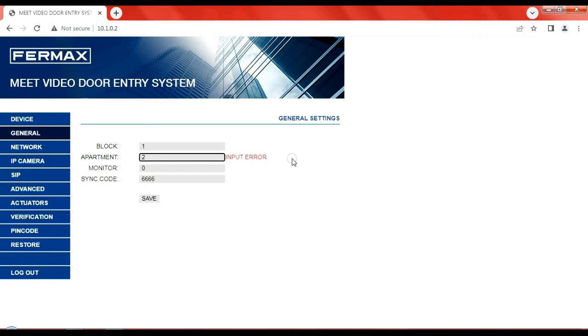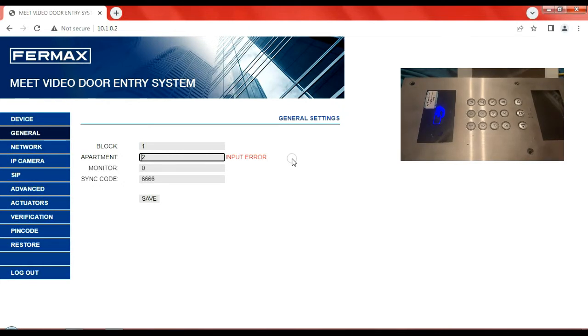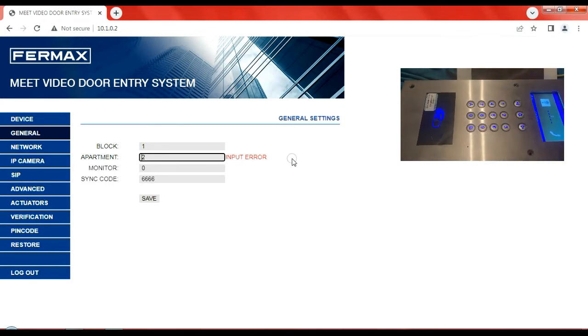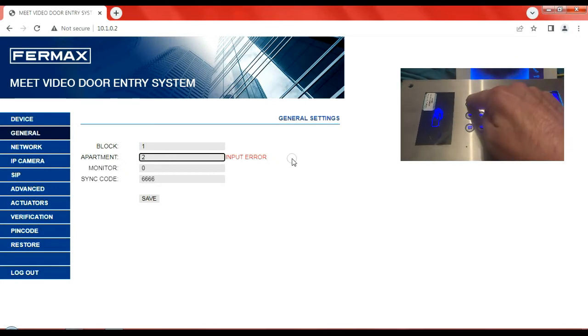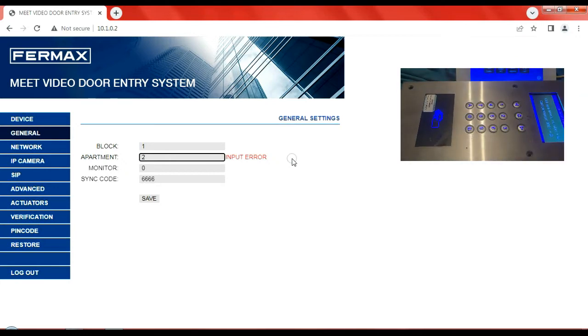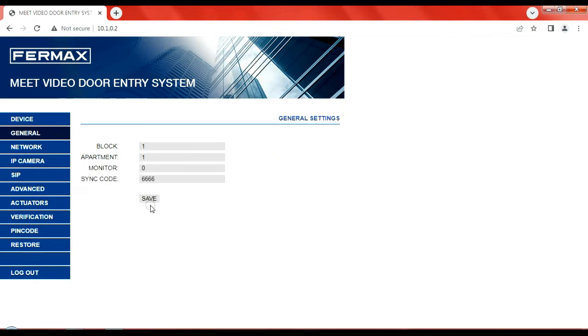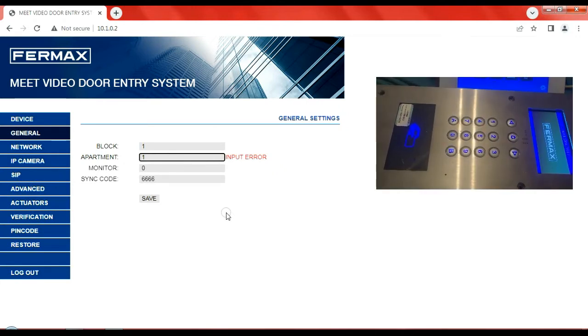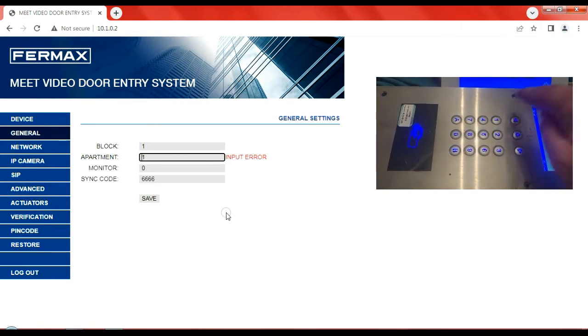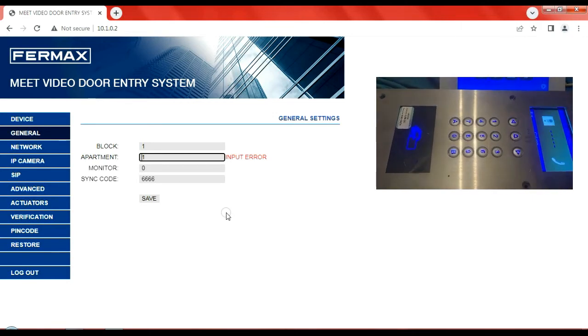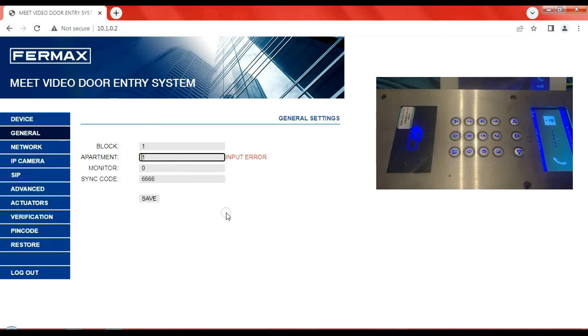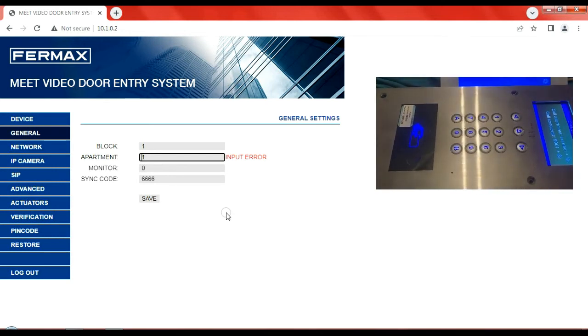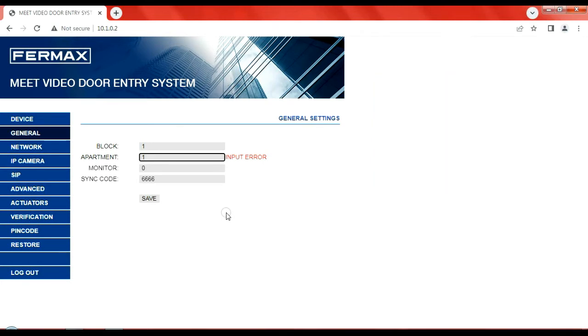It says input error. You'll have to take my word for this, but if I press 2 and then call, you can hear the door stations ringing and also the handsets ringing. Then I press A to cancel the call. So if I go to this again and change this to 0001, for instance, press return and then save, it still comes up as an input error. However, if I press 2 now again, there's no one there. If you press 1 and then call, you can hear that we have changed the address of the phone. So that's the general information.